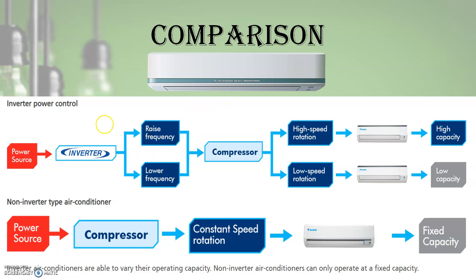With the inverter, speed control is done to achieve temperature control. It can operate at high speed by making the frequency high, or at very low speed by making the frequency lower — so capacity can vary from high to low. For example, a 1.5 ton inverter AC can work from 0.3 to 1.7 ton based on cooling requirement, whereas a non-inverter AC can only work at a fixed 1.5 ton.